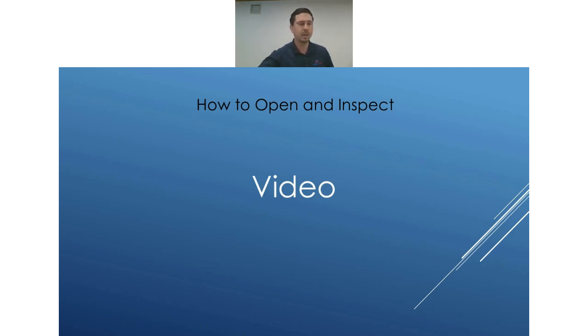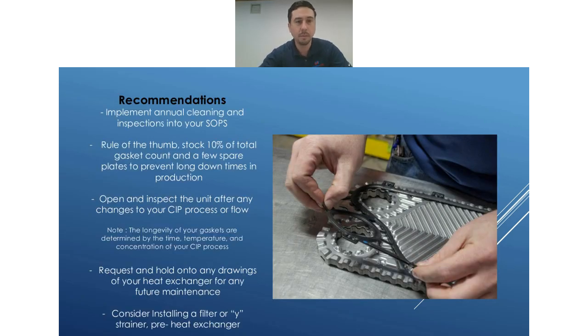So we're going to look at some of the recommendations we make for your plate heat exchangers. One thing you want to do is enter a set date and time in your SOPs for annual cleaning. A lot of times, if it's not written in stone, if it's not somewhere, it gets forgotten. So we want to make sure we get that in our SOPs so we know there's a documented time when we are to open and inspect that heat exchanger.